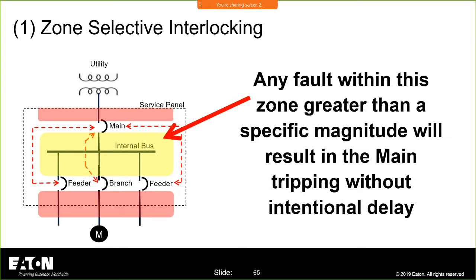That's what ZSI gets you in the zone of protection. Any fault in that zone will trip without an intentional delay, but because of the brain we talked about earlier, it'll typically take around 0.07 seconds. Now, nobody's asked the question. I haven't seen it. Where did 0.07 seconds come from? Right here, you're looking at it.